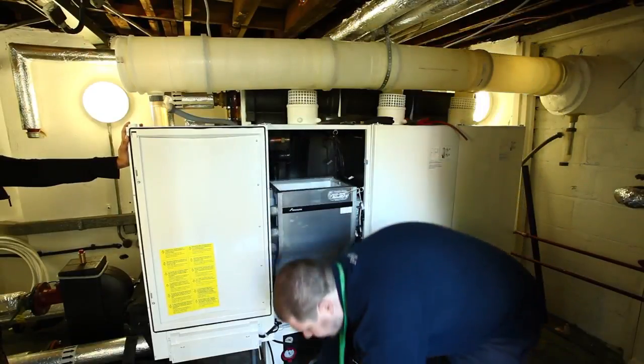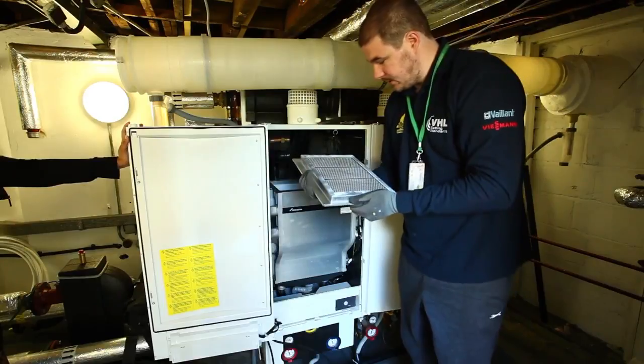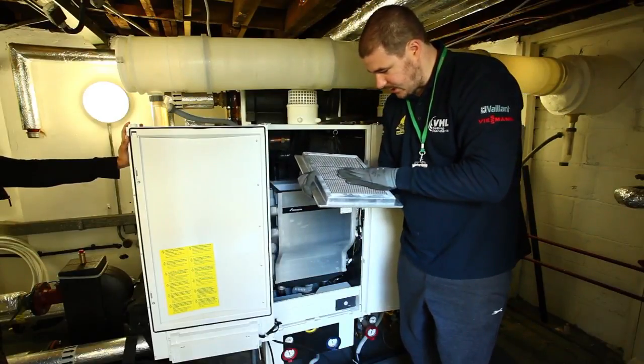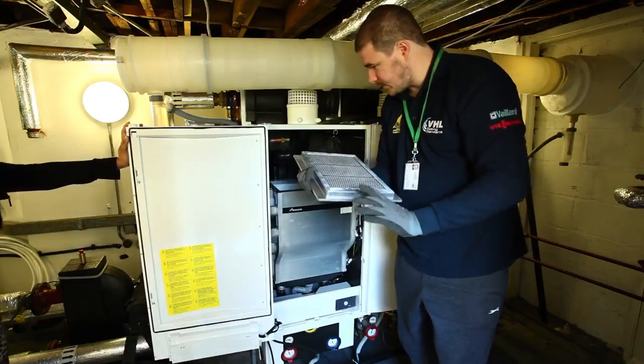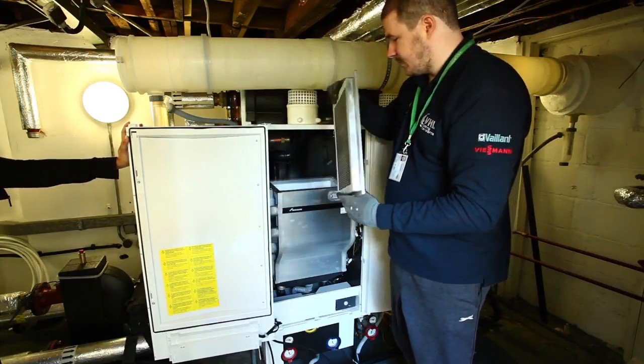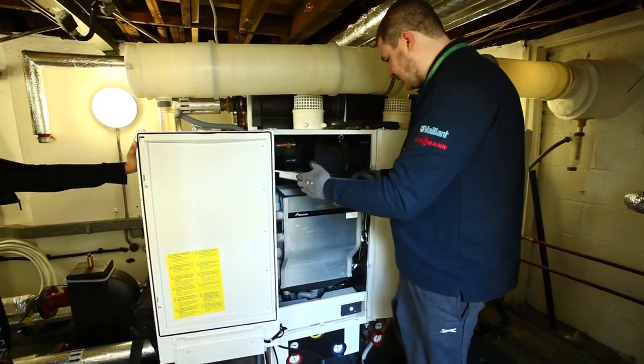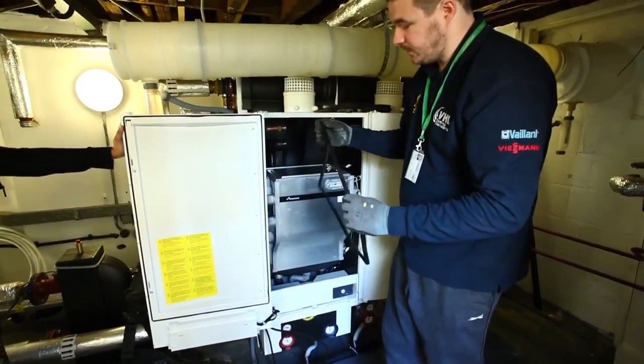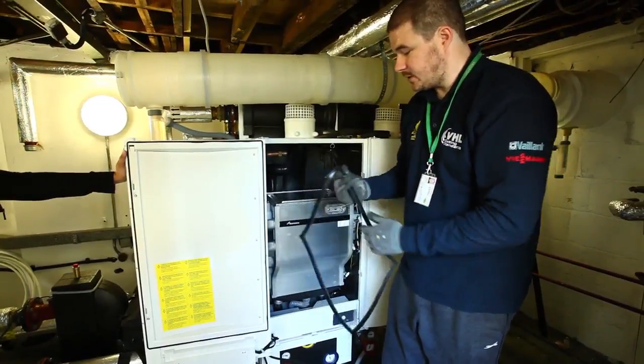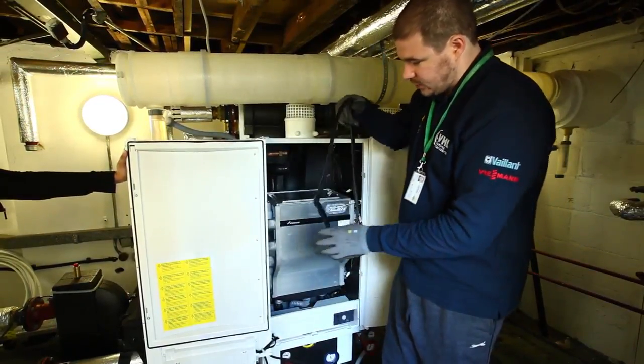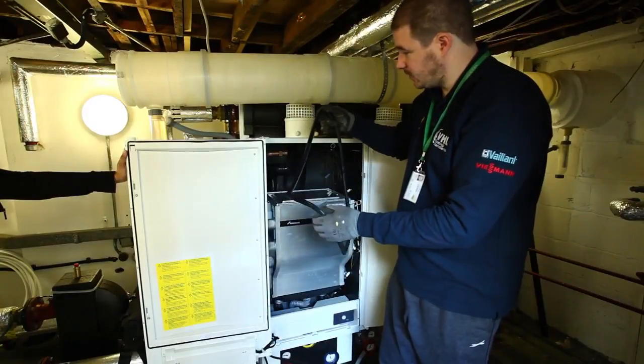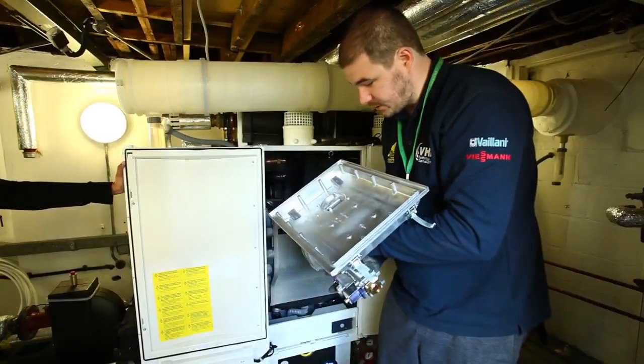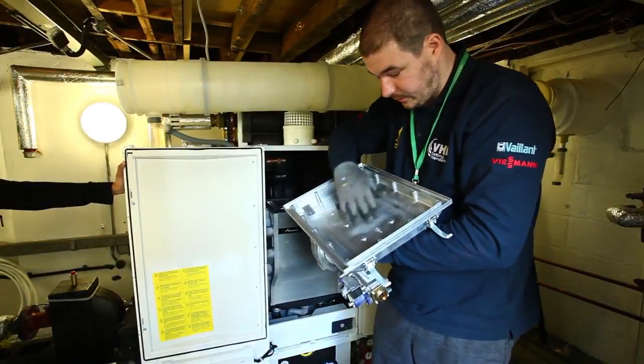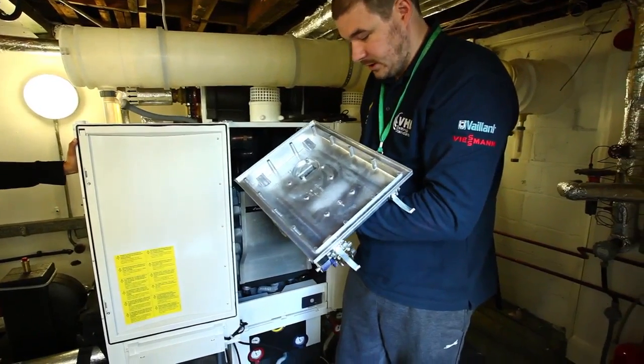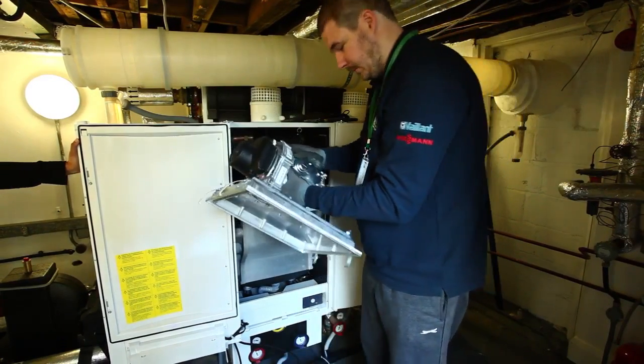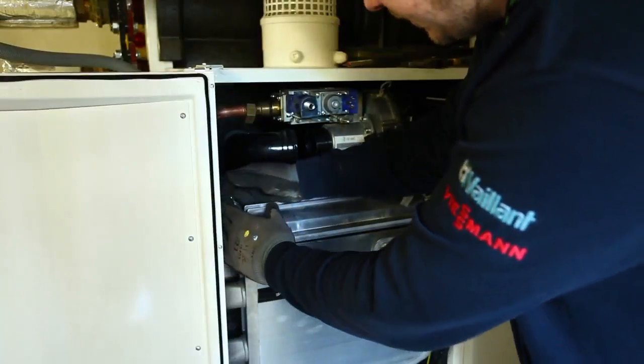So the first thing we put back is the burner. Just check it to make sure there's no dust and very lightly wiping it. After we're happy with that, we then place it back into the boiler very carefully because it is ceramic. We re-inspect the seal, or we will change it in the case of a service, just making sure that it's nice and flimsy, so it's nice and soft and it's going to form a good combustion seal on the boiler. Just a minor inspection for any dust particles that may have come through. As we can see, there's not much here, and then we reinsert it back into the boiler. Once we're happy with it, just simply fix back in again.